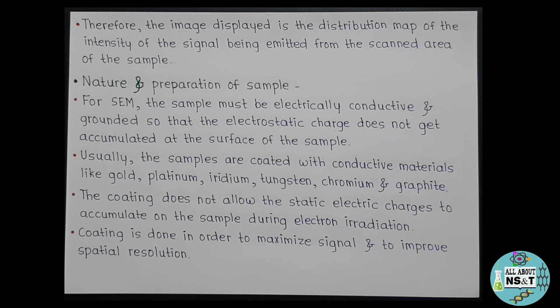For SEM, the sample must be electrically conductive and grounded so that the electrostatic charge does not get accumulated at the surface of the sample. Usually the samples are coated with conductive materials like gold, platinum, iridium, tungsten, chromium, and graphite. The coating does not allow the static electric charges to accumulate on the sample during electron irradiation. Coating is done in order to maximize signal and to improve spatial resolution.